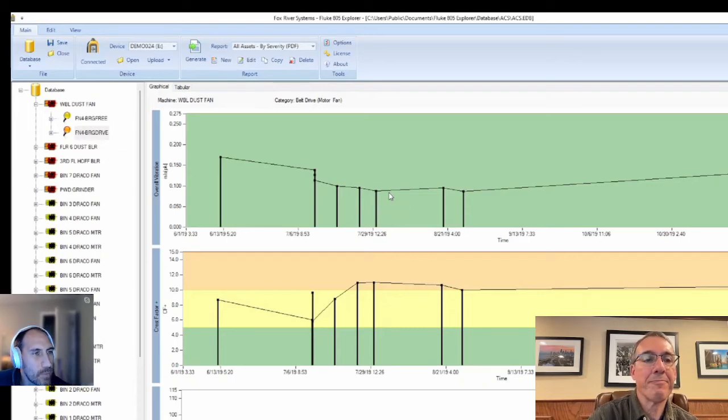One thing I noticed that this brings, a lot of capability the 805 currently doesn't have, is that you can have multiple bearings on a single asset. I'm not so sure you can trend that in the 805 anyway. I think of it as a single bearing use for each one, whereas you're putting multiple bearings in a single asset, and that asset gets called out even if it's just one bearing in the asset, which is pretty unique.